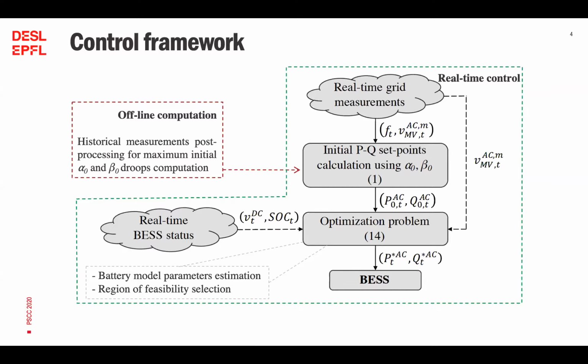The scheme in this slide represents the conceptual framework of the controller. As you can see, initial alpha and beta droop values are used to compute the initial active and reactive set point that will be actually the input of our optimization controller. In fact, this set point will be compared with the corresponding feasibility region for that particular real-time status of the battery and the real-time status of the grid. So, with our proposed method, we can predict the AC and the DC voltage in a parametric way, and we can pick the corresponding correct capability curve, and finally send the calculated active and reactive set point to the battery system.